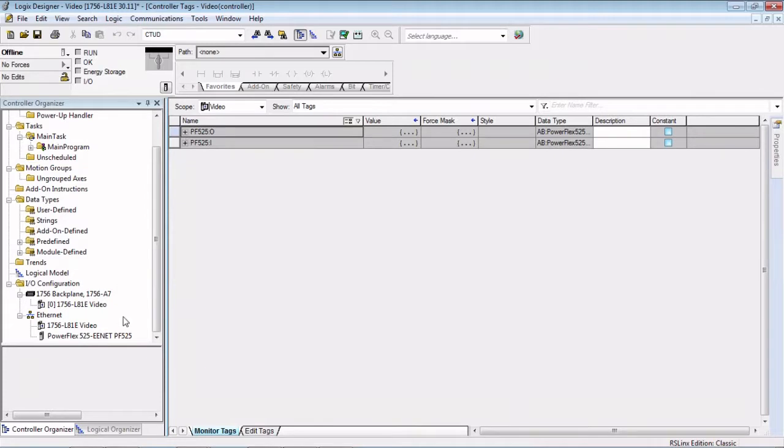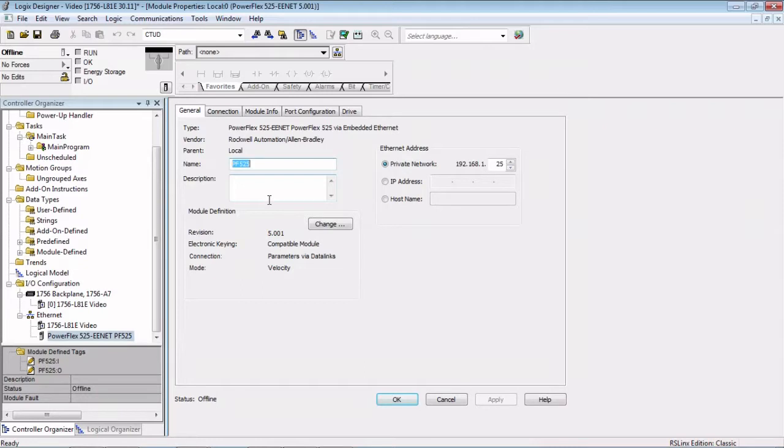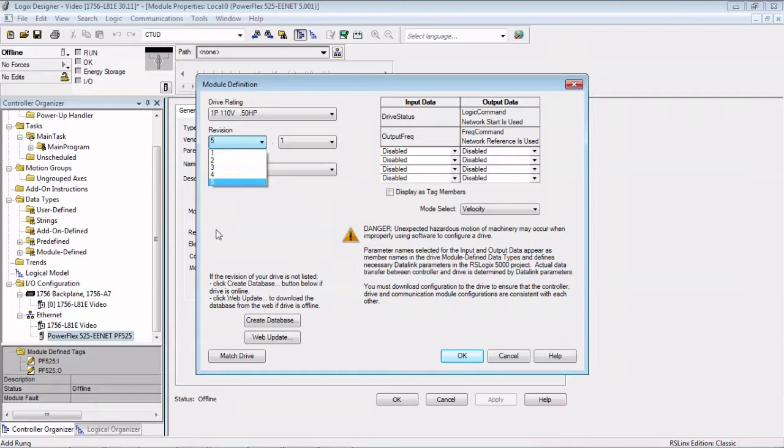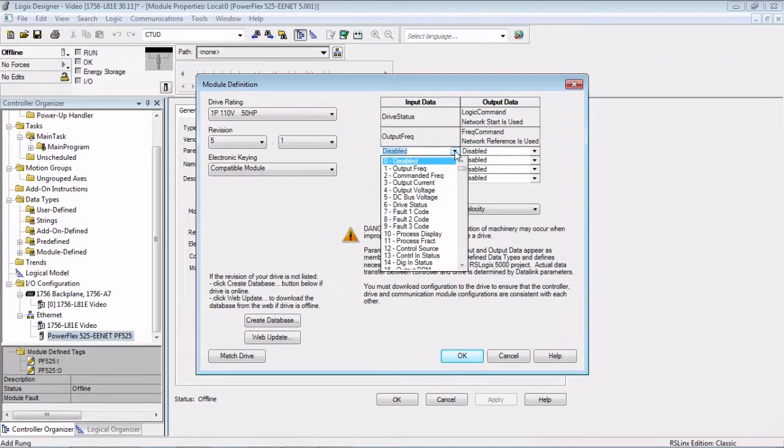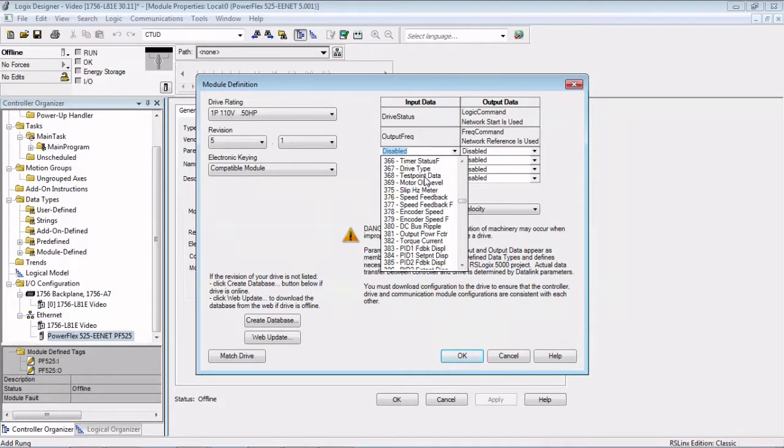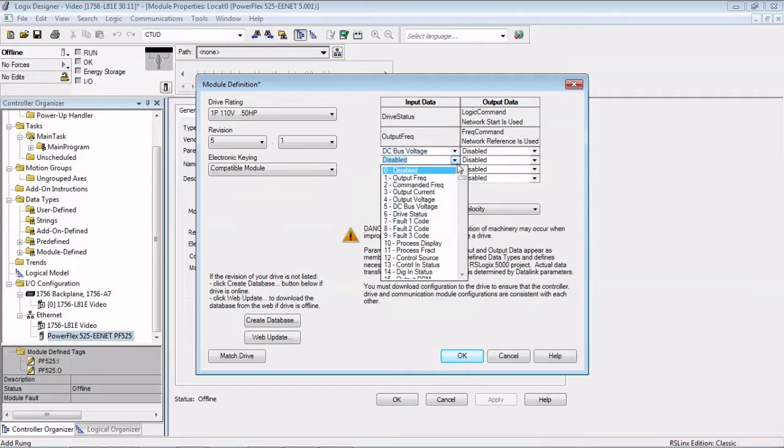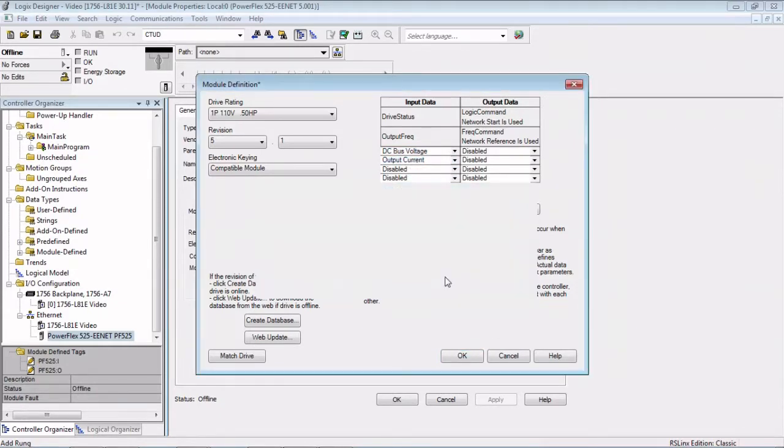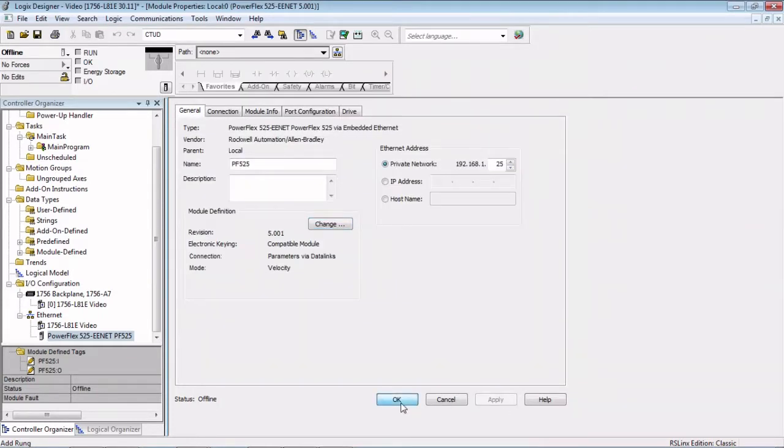Let's say that you wanted to monitor something else besides what's given to you by default. Say you wanted to monitor the DC bus voltage or the output current. We could double click on the drive in the tree, it brings up the configuration screen. Under module definition, we're going to click this. This is also where you would change the revision of the drive to match the one that's out on your network as well as the drive rating for power. But over here on the right, you can see we have four words in and out that we can use. If we click on the arrow here, we can grab any parameter in that drive and bring it back into our controller just this easy. So we're going to grab the DC bus voltage and the output current. Hit OK, yes, apply, OK.